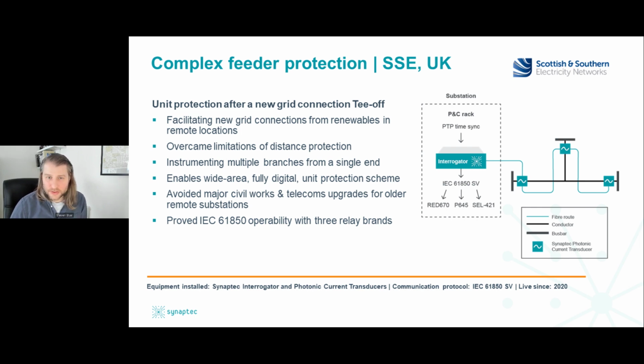In this case, this approach allowed new teed connections, which are typically going to be from large wind farms being connected into the grid, to be very cost effectively protected. Otherwise, a lot more infrastructure would be required to support relays and provide auxiliary backup supplies and everything else that would be needed. This also, importantly, avoids some of the compromises of distance protection, where it can be very difficult to set the settings and then prove that they are correct for all possible scenarios, whereas this relies just on the tried and tested approach of differential protection.